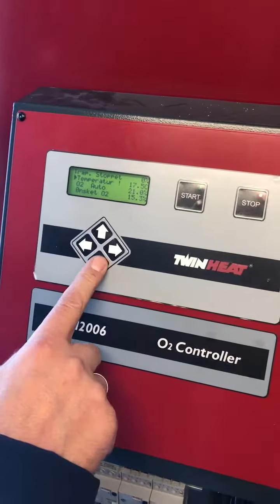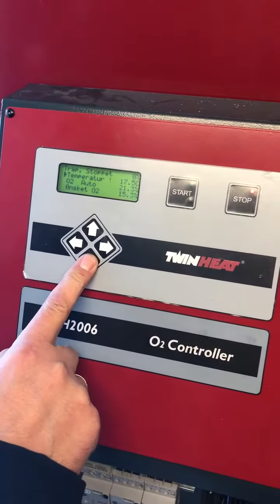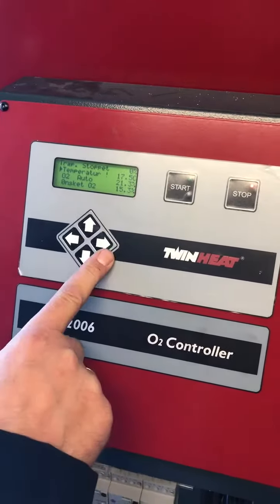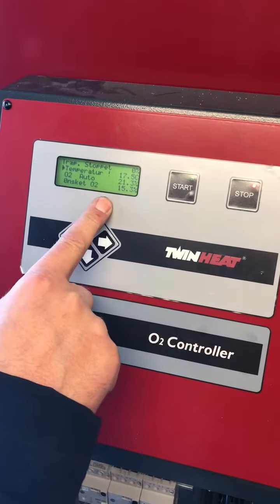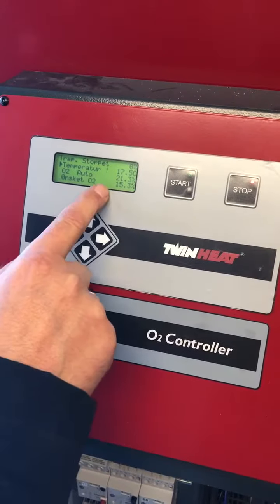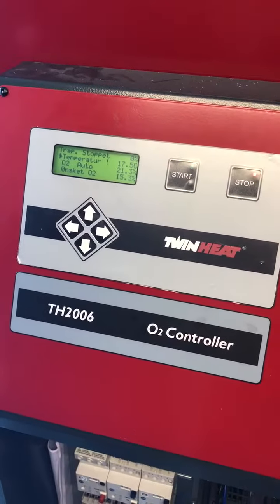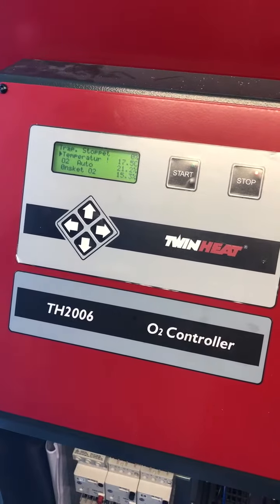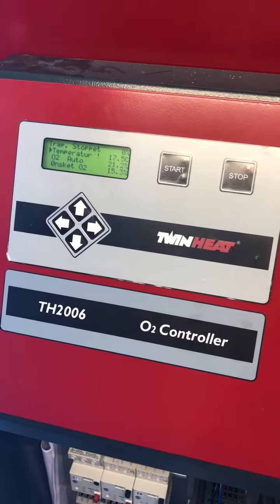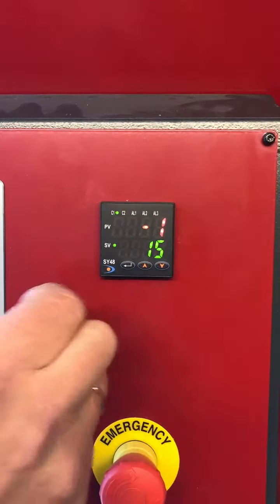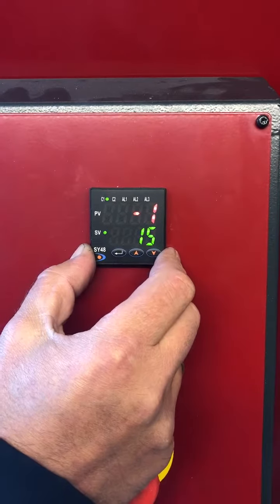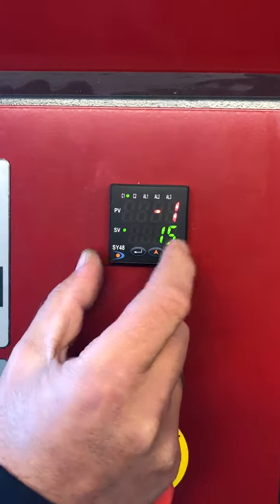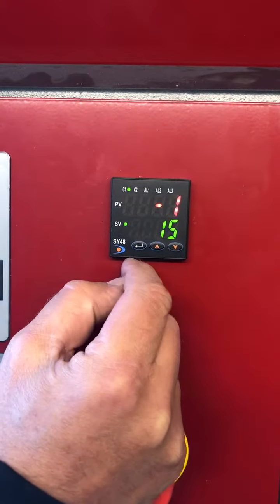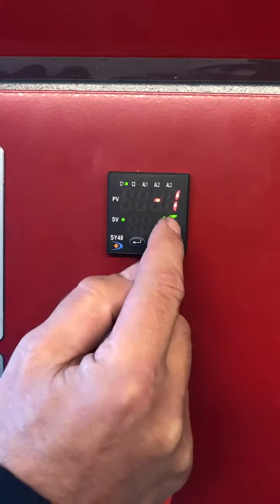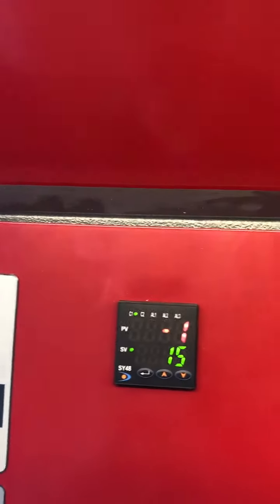Sorry, the text is in Danish at the moment. Hopefully that's okay. This is a lambda probe regulation, and it's regulated after the O2 value, which is regulated after the output of the boiler. Here we have the display for regulating the fan on the chimney. And here we've set it on, we want 15 Pascal under pressure in the boiler. We can't test it now because the chimney is stopped.